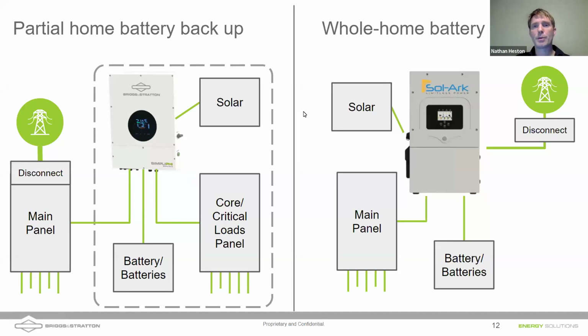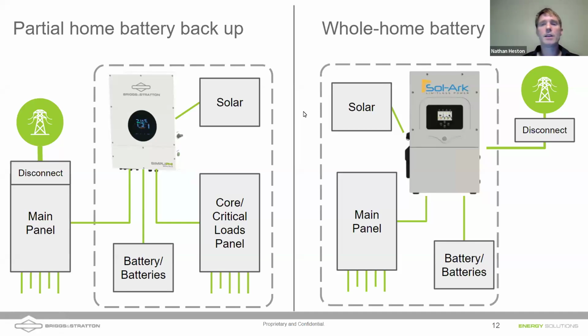Let's look at the home battery backup on the right side of the screen. We're looking at a Sol-Ark 15k, and essentially this inverter would, I'm sorry, my dashed line is not perfect there, but we would disconnect from the grid on the right. So if you see the grid coming in on the right side, we would disconnect from the grid there and isolate that inverter, but all the loads in the home would be on that critical loads panel.